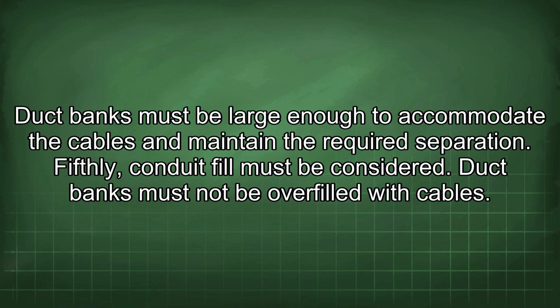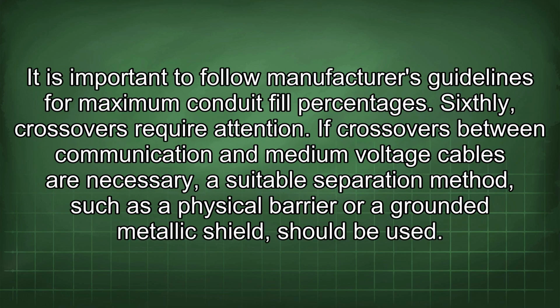Fifthly, conduit fill must be considered. Duct banks must not be overfilled with cables. It is important to follow manufacturers' guidelines for maximum conduit fill percentages. Sixthly, crossovers require attention. If crossovers between communication and medium voltage cables are necessary, a suitable separation method, such as a physical barrier or a grounded metallic shield, should be used.